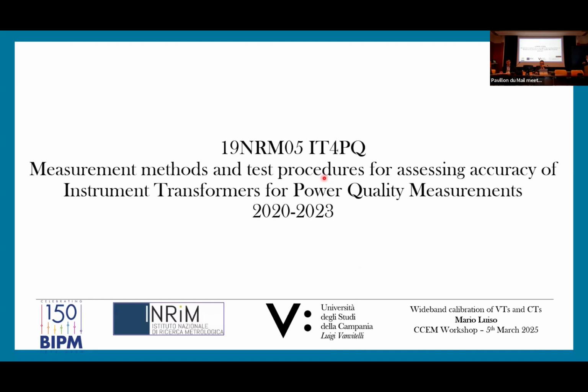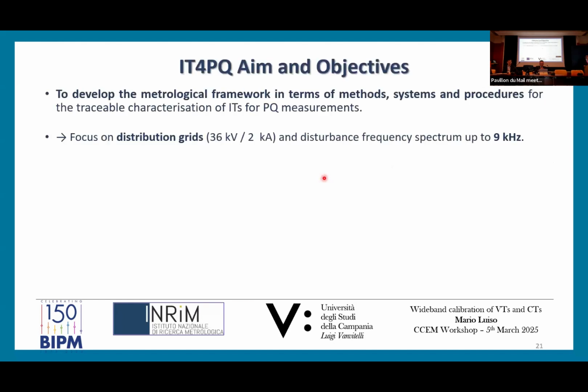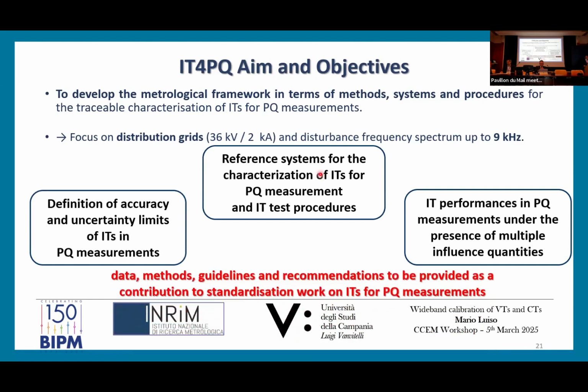So in the rest of this presentation, I will talk about the main results of IT4PQ and the first results of the ADMIT project. The aim of the IT4PQ project was to develop the metrological framework in terms of methods, systems, and procedures for the traceable characterization of instrument transformers for power quality measurements. And the focus was on distribution grids, so 36 kilovolts and 2 kiloamps, with disturbance frequency up to 9 kilohertz. The data and the findings were transmitted to the IEC TC 38 committee that was the chief stakeholder for this project.